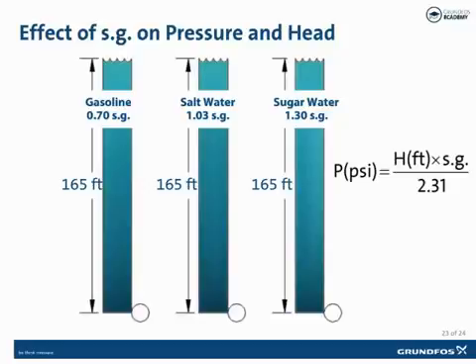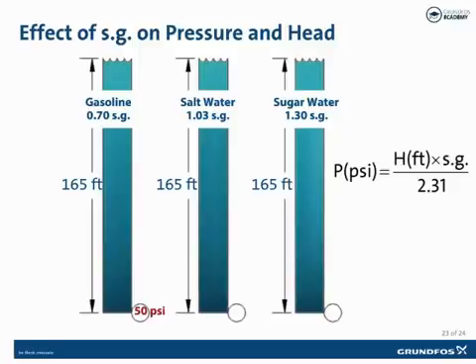Now let's look at what effect the specific gravity of a fluid has on pressure head. If we had a column of gasoline with a specific gravity of 0.7 that was 165 feet tall, the pressure gauge at the bottom would read 165 times 0.7 divided by 2.31, giving us 50 PSI. A column of salt water with a specific gravity of 1.03 at 165 feet tall would read 165 times 1.03 divided by 2.31, giving us 74 PSI. A column of sugar water with a specific gravity of 1.30 at 165 feet tall would read 165 times 1.30 divided by 2.31, giving us 93 PSI. Fluids with a higher or lower specific gravity than water can cause changes in how a pump operates.